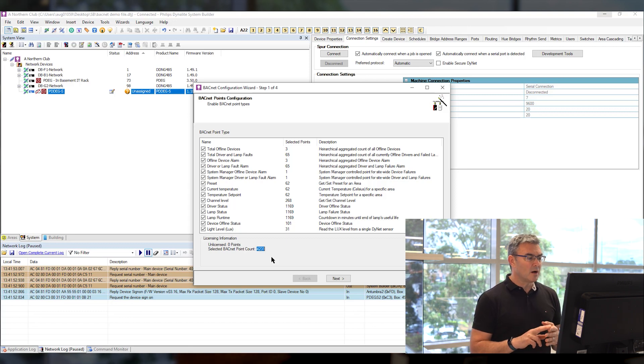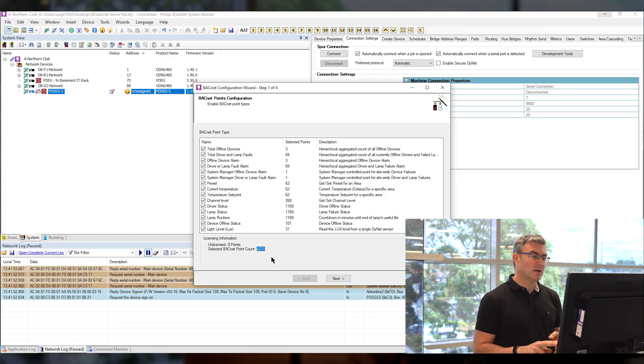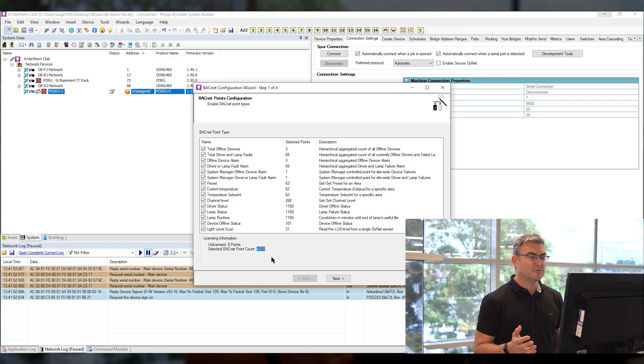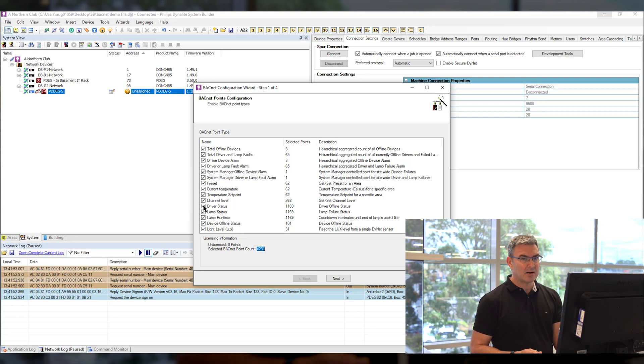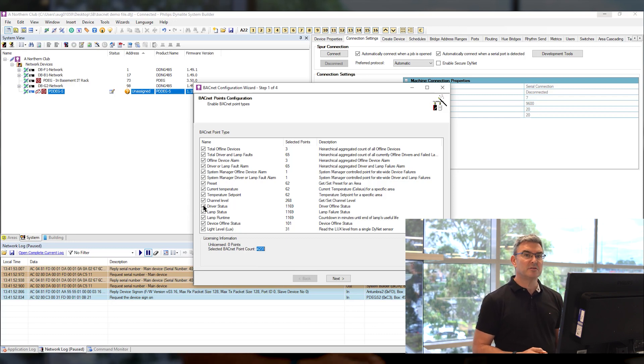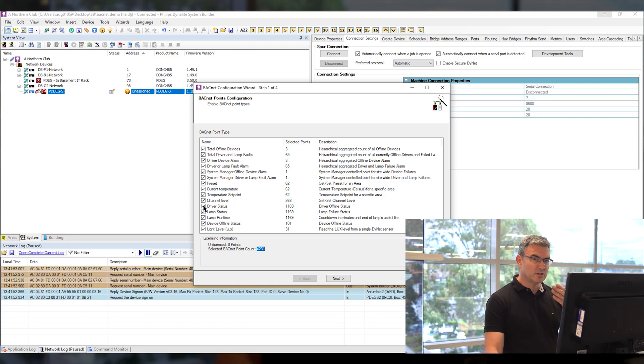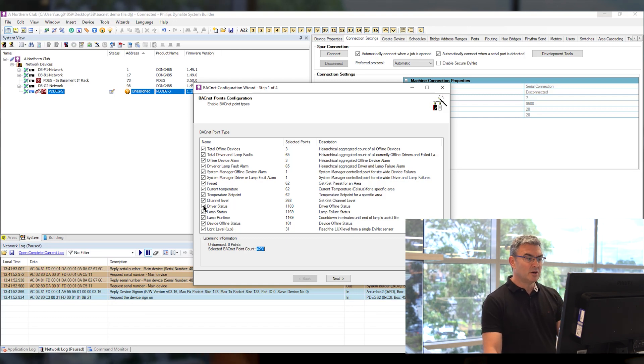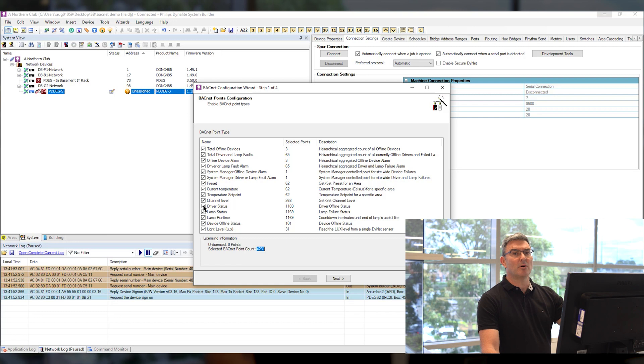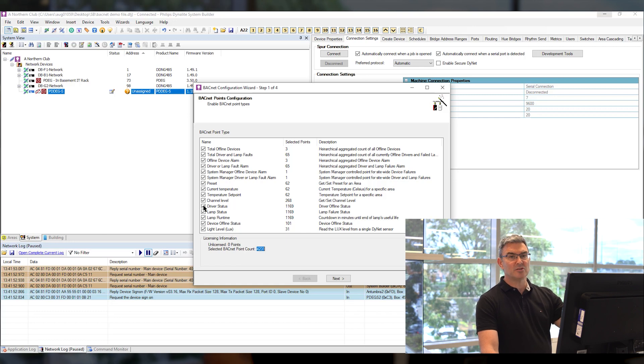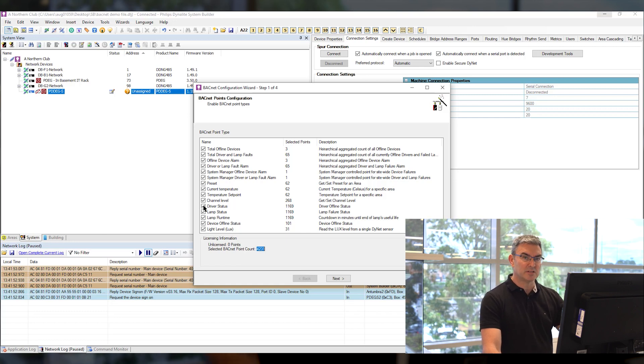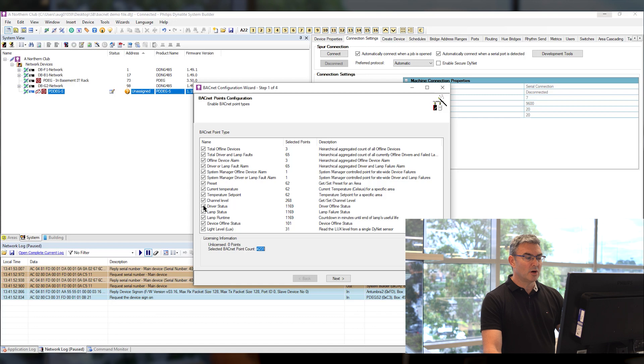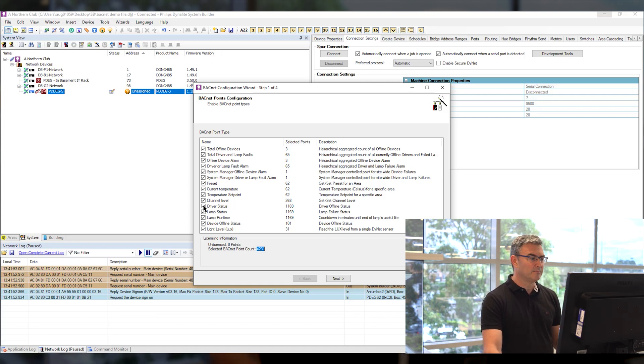If costs or the budget is tight or just for good practice you can start removing at a macro level large chunks of these points to bring your point count down. Remember of course there's a cost to buy the license but there is also a BMS cost to set up each of these points on the other end so you don't want any redundant points that's just a waste of time and money.